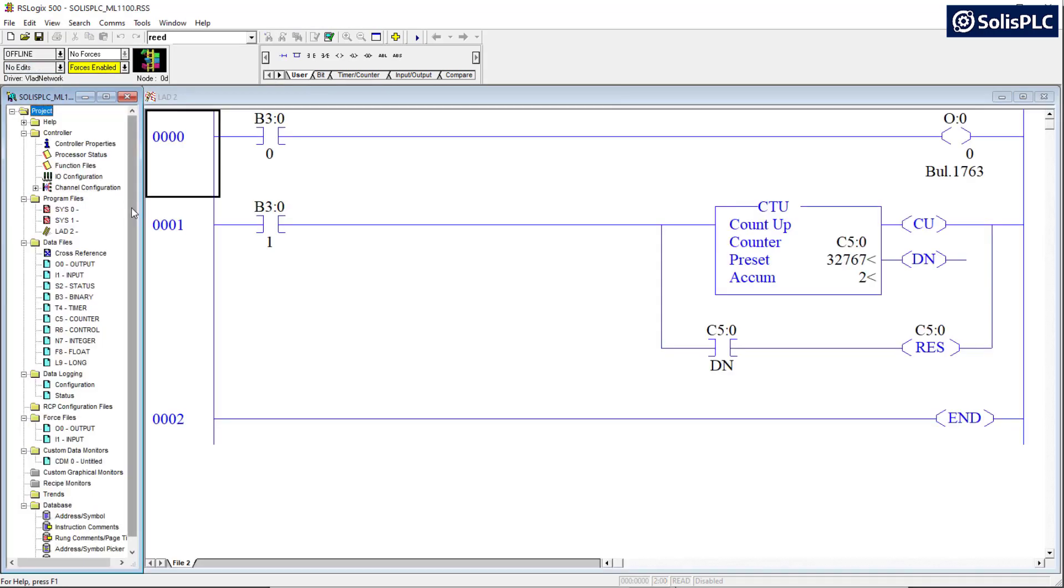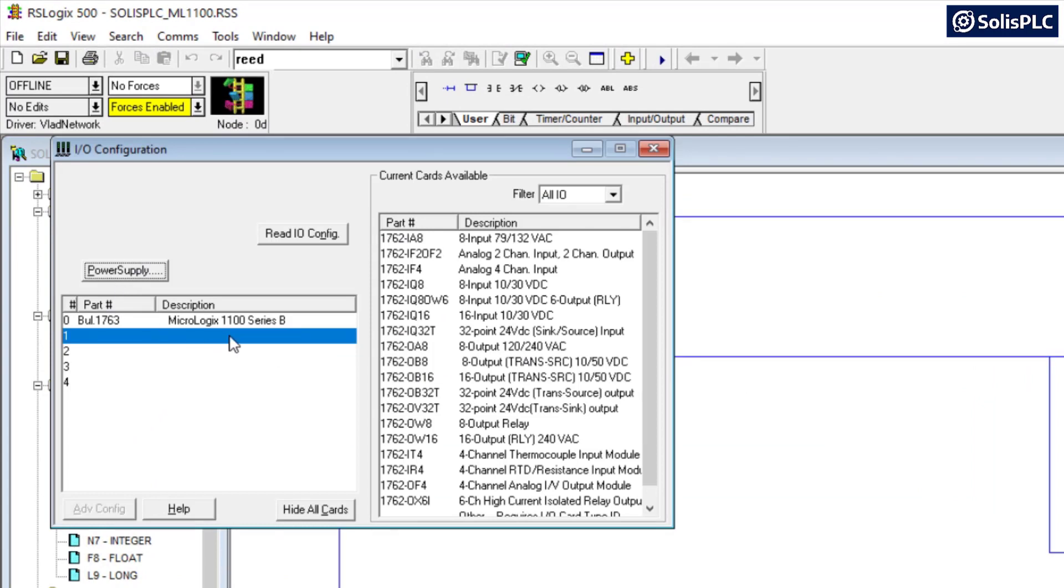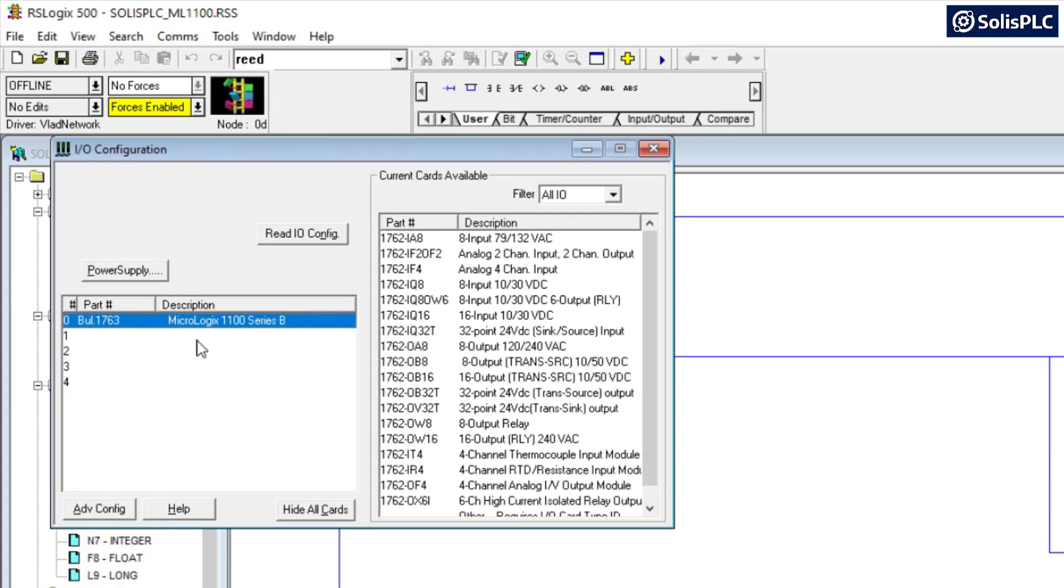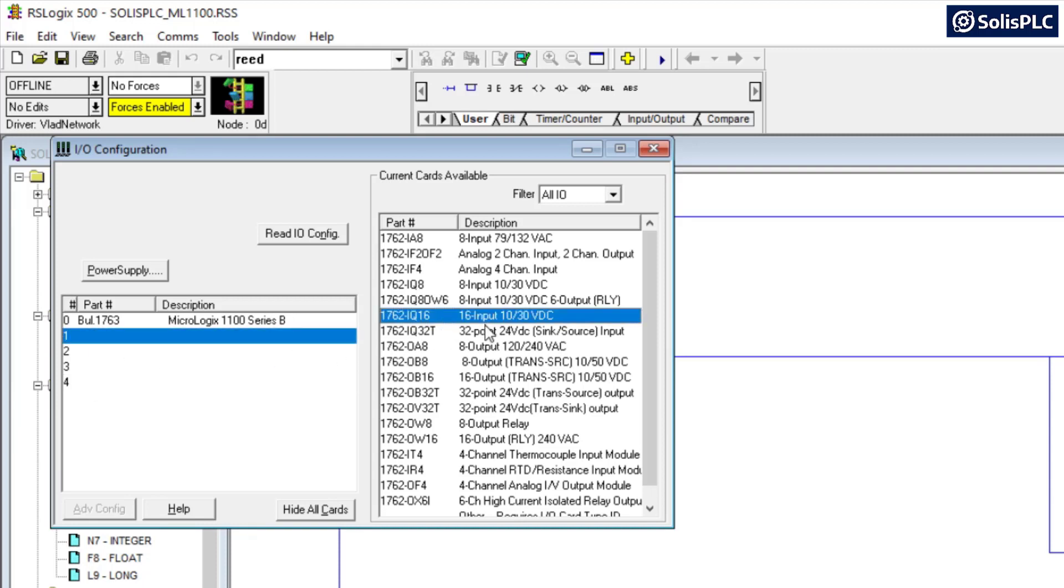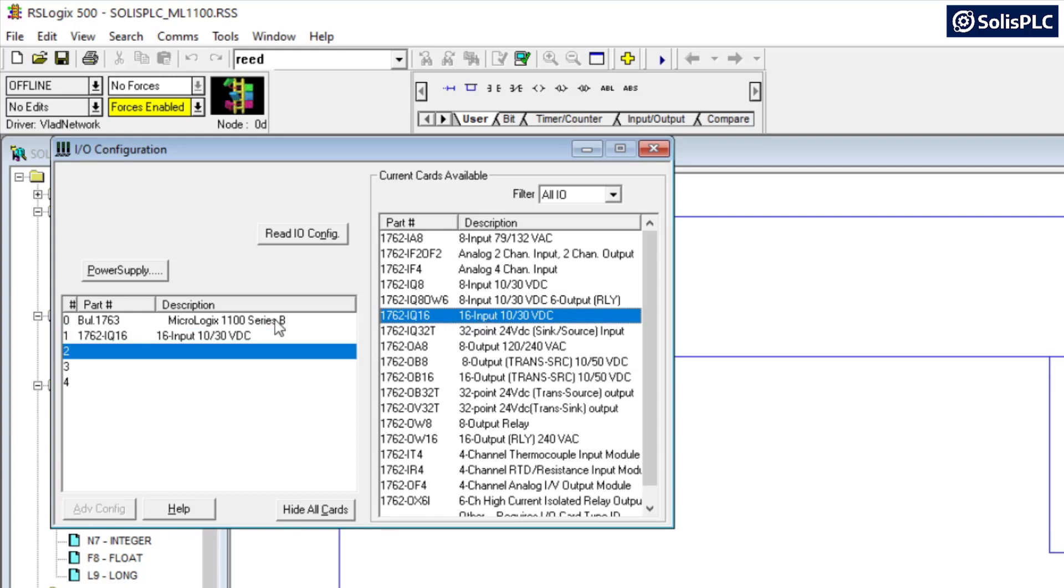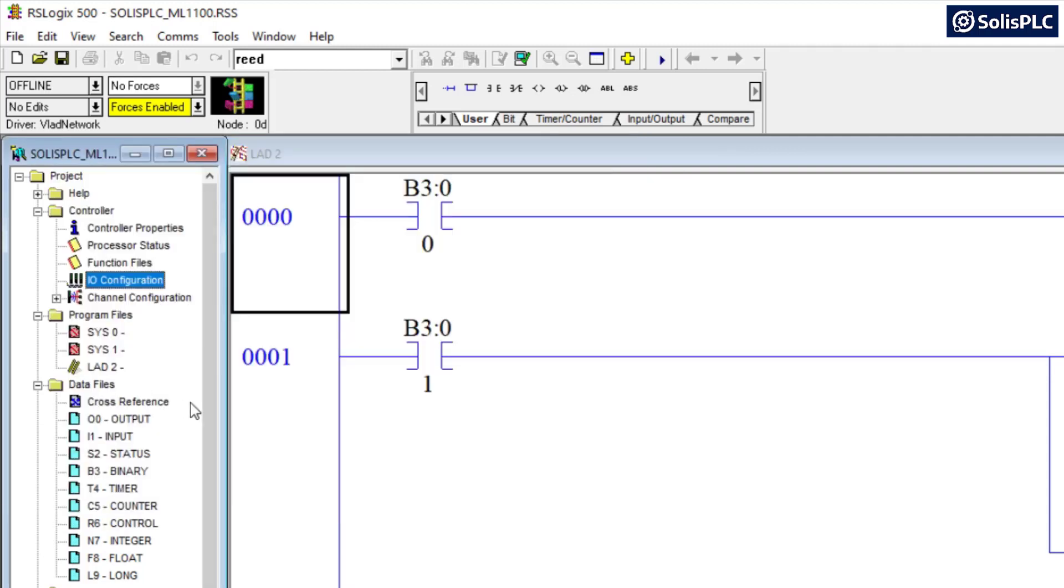I'm going to go offline by clicking on this remote run, go offline. And here we're going to enter I/O configuration. So double click I/O configuration. You'll notice that the slot number zero in this case is going to be MicroLogix 1100 series, which is our PLC. And next, we've got four empty slots. So we can start by entering the card that we've looked at just a few minutes ago. That's the 1762-IQ16, or the 16 input 10 to 30 VDC input card. By double clicking that or by dragging it out to the slots, you'll notice that it has been placed in slot number one, which is where it currently resides. The card has been set. We can close out of this menu by clicking this little X.